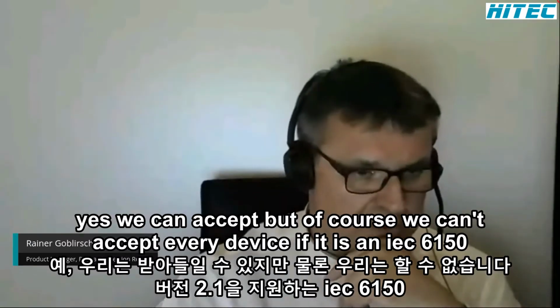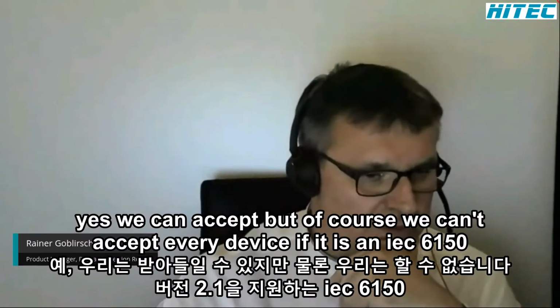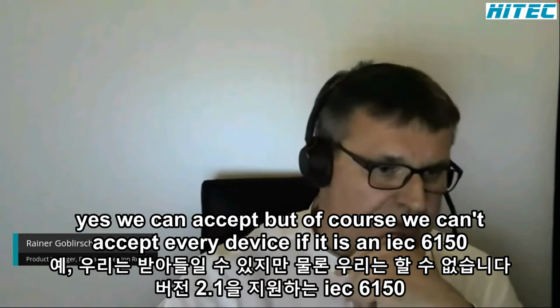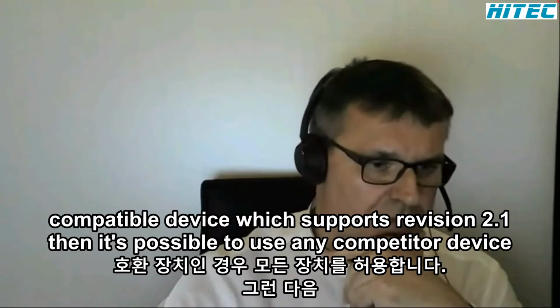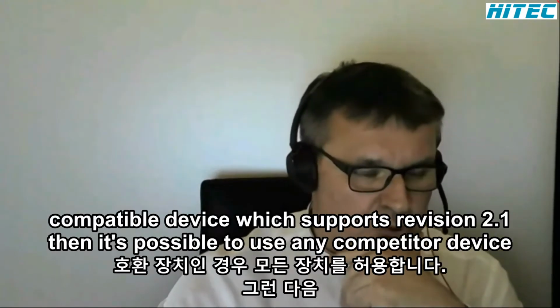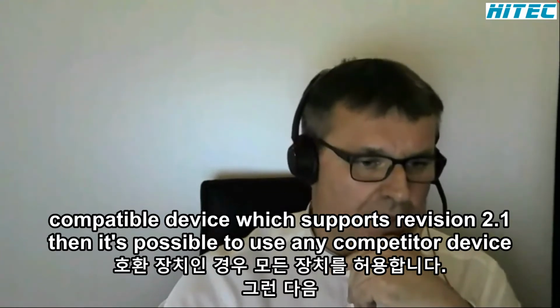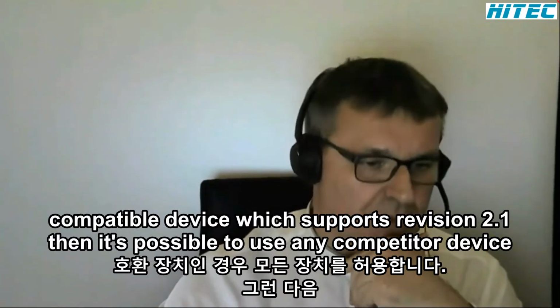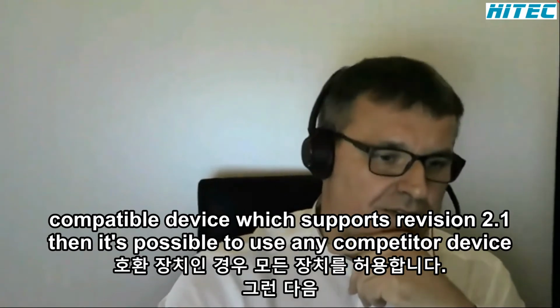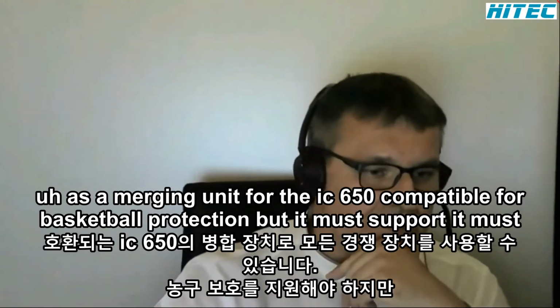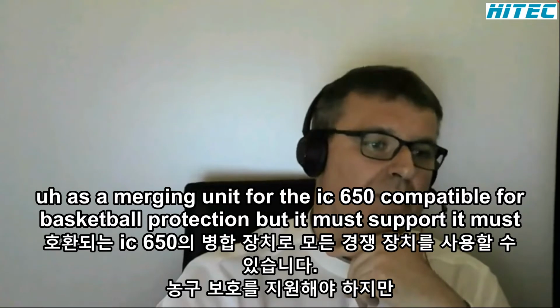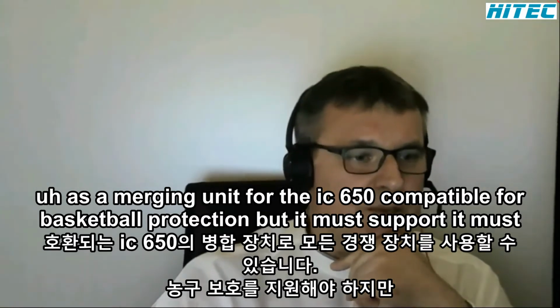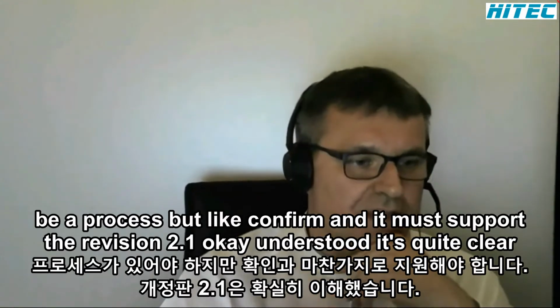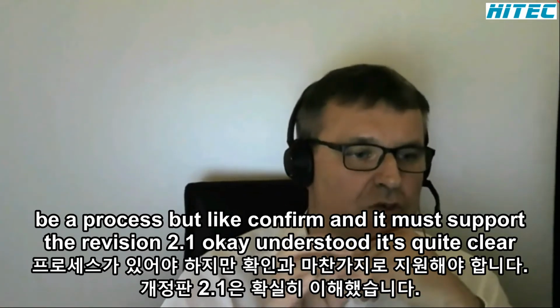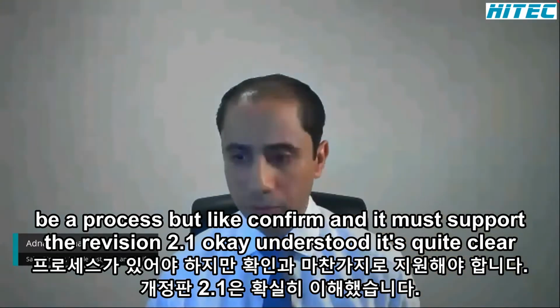Yes, we can accept, but of course we can't accept every device. If it is an IEC 61850 compatible device which supports revision 2.1, then it's possible to use any competitor device as a merging unit for the IEC 61850 compatible busbar protection. But it must be process bus conform, and it must support revision 2.1. Okay, understood. It's quite clear.